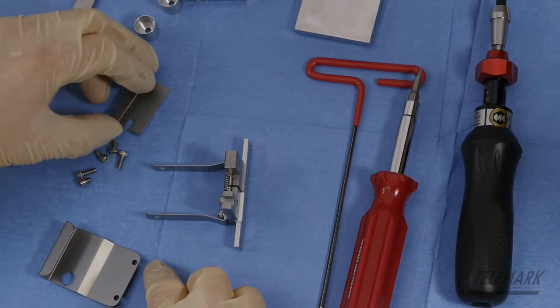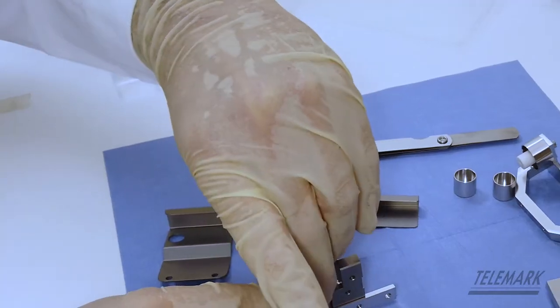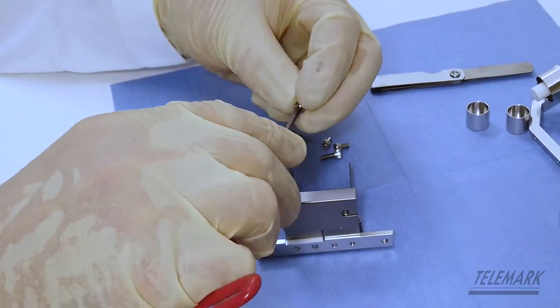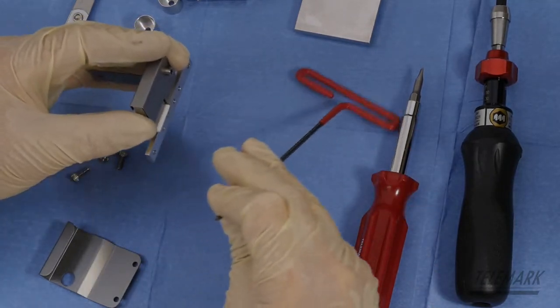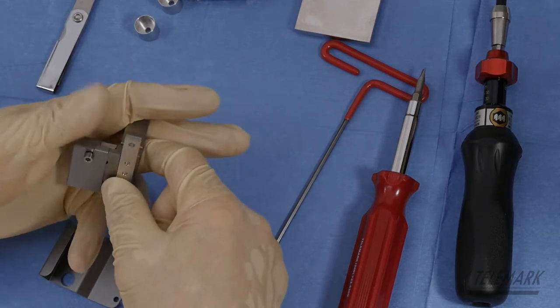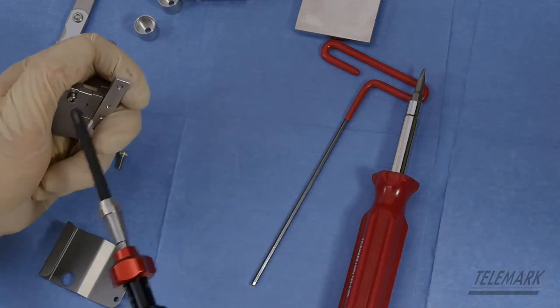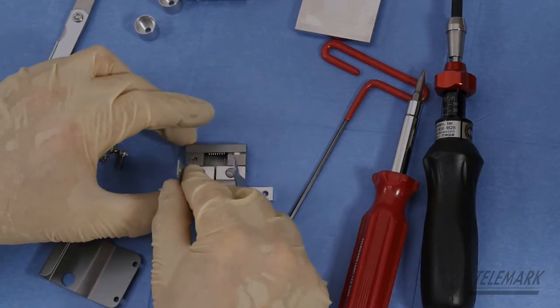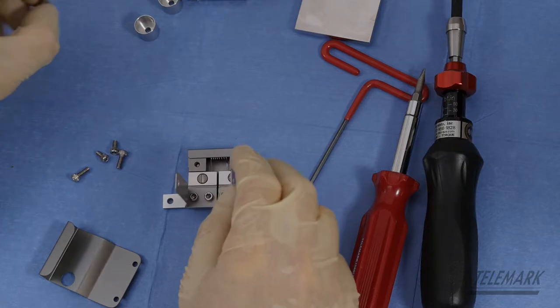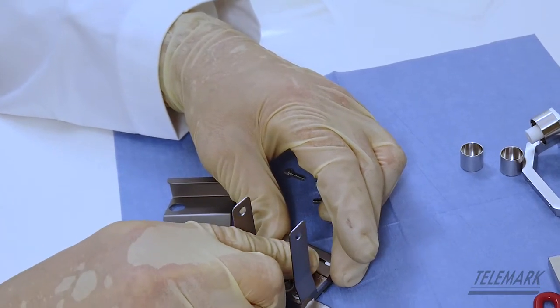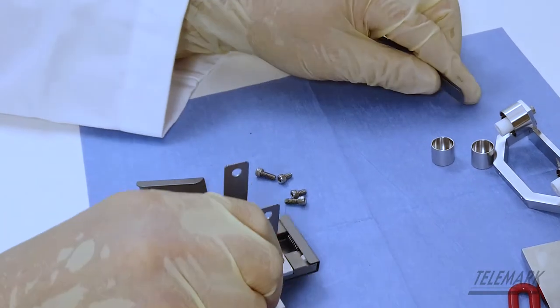Locate your beam former and insulator cross. Put that in its home, place your beam former, and grab your Allen wrench. You should have one last titanium screw, 3/16. Snug that into place. Grab your torque wrench and put your thumb on the side, pushing to the side and down to square it up against the cathode blocks. Lock that down. Check your filament to make sure you're square in there. The gap between the beam former and filament windings should be 25 to 30 thousandths, and we're set at 30.